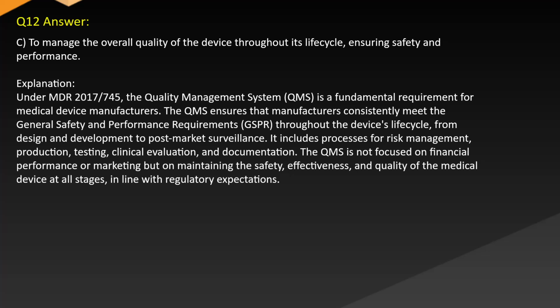Explanation. Under MDR 2017-745, the quality management system, QMS, is a fundamental requirement for medical device manufacturers. The QMS ensures that manufacturers consistently meet the general safety and performance requirements (GSPR) throughout the device's lifecycle, from development to post-market surveillance. It includes processes for risk management, production, testing, clinical evaluation, and documentation. The QMS is not focused on financial performance or marketing, but on maintaining the safety, effectiveness, and quality of the medical device at all stages in line with regulatory expectations.